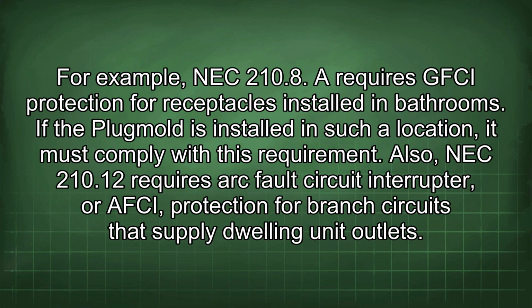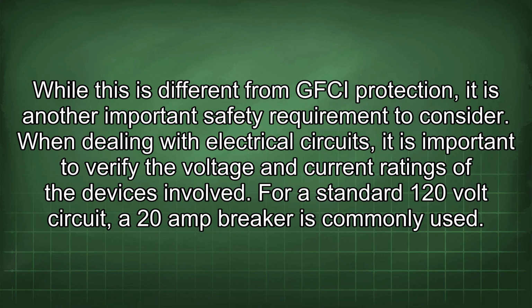For example, NEC 210.8 requires GFCI protection for receptacles installed in bathrooms. If the Plugmold is installed in such a location, it must comply with this requirement. Also, NEC 210.12 requires arc fault circuit interrupter, or AFCI, protection for branch circuits that supply dwelling unit outlets. While this is different from GFCI protection, it is another important safety requirement to consider.